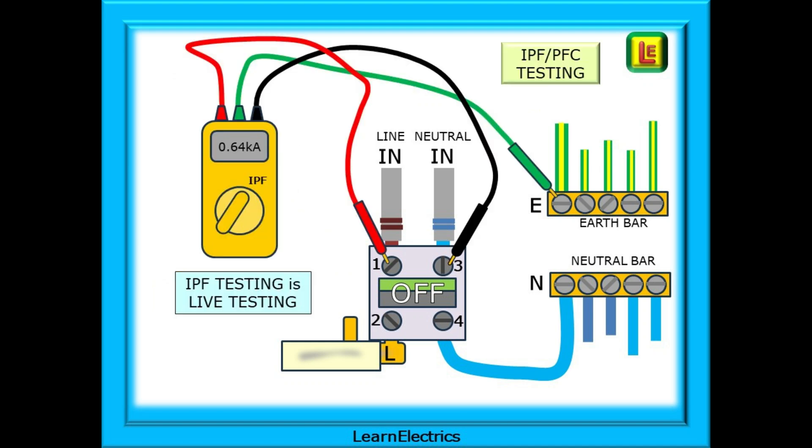To carry out the IPF test, set the meter to the correct range and test between the incoming line terminal and the earth bar. Shown here is a three-lead test, which includes a probe on the neutral bar. Some more modern meters will only require a two-lead test, the line and earth connections. Get to know your meter before assessment days.